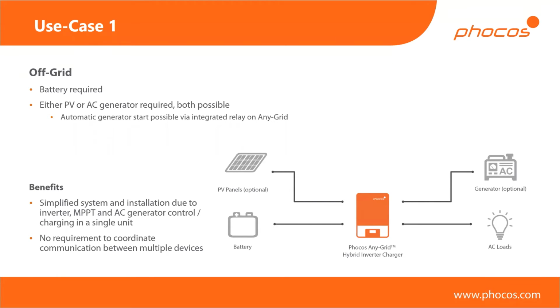So use case number 1, this is an off-grid use case, so you can see that there's no grid connected here. We do require a battery in this case, and you're going to need either PV as an energy source or an AC generator like a genset, for example. You can start that automatically by the relay described earlier. So the benefits of this kind of system is that you have a vastly simplified system as compared to your traditional inverter plus charge controller plus potentially charger from the grid. So you're combining at least 3 devices into one, and that's not to speak of the whole synchronization and fast switching, etc. So you're really simplifying that down into a single device.